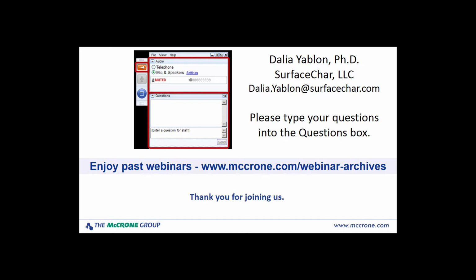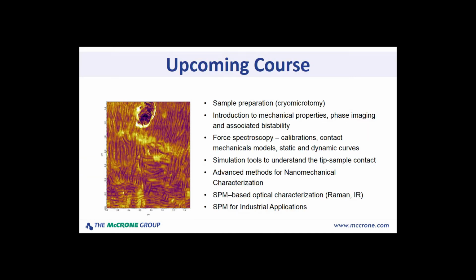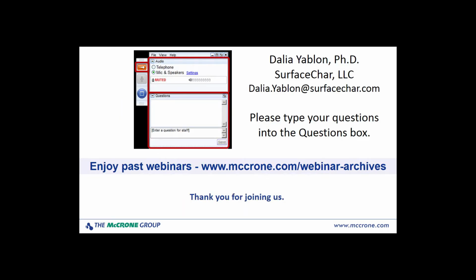The first question is what are the constraints on a sample that you can measure with AFM? Excellent question. So there are basically two main constraints. The first one, it has to fit into the instrument. Not a surprise, it's a microscope. AFMs actually come in two types, a small sample instrument, which maximizes on the signal to noise, and a large sample instrument to accommodate large samples. So I would say as long as your sample can fit into the instrument, you should be okay. And if you have a challenging geometry or a large sample, you might have to go to a large sample AFM. I can tell you that when I was at ExxonMobil, some of the most exciting samples I personally worked on were engine parts that we would look at.